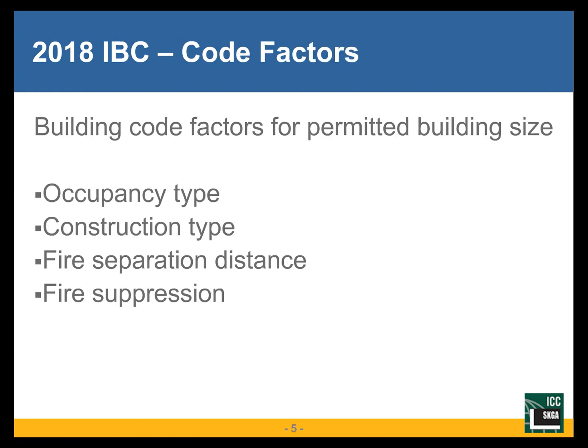When looking at the parts of the building code relevant to fire resistance, the key factors are: occupancy type, construction type, fire separation distances from adjacent properties, and any fire suppression placed in the building such as automatic sprinkler protection. These factors all play a part in how the code determines what kind of fire resistance ratings may be required for the particular building under consideration.